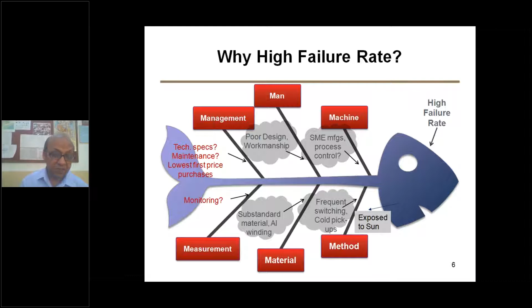Now, to see these particular examples which we collected in our study, what is happening in the failure of the transformer. When you look at the failure of this transformer, see over here, you are looking that between two spacers, there are failures. Everywhere you see between two spacers, there is a failure in ST winding. Between two spacers, failure is happening. Now you have to look at why it is happening between two spacers.